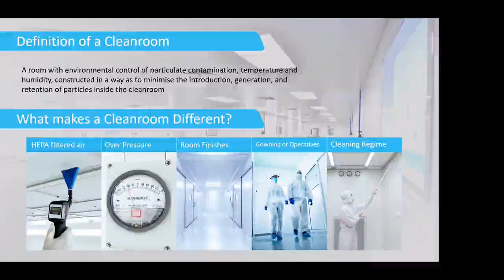So in terms of classifying a room, there's 2 key regulatory characteristics that are applied. One is GMP, which is good manufacturing practice. That's primarily used for anything involving human medication, so vaccines, medicines, medical devices. The other set of classifications is the International Standards Organization. That's more used for manufacturing devices, jet engines, microchips, things like that. But they both pretty much work off the same standard, which is counting the number of particles in a cubic metre of air and then reading that number off in a table and classifying the cleanliness.